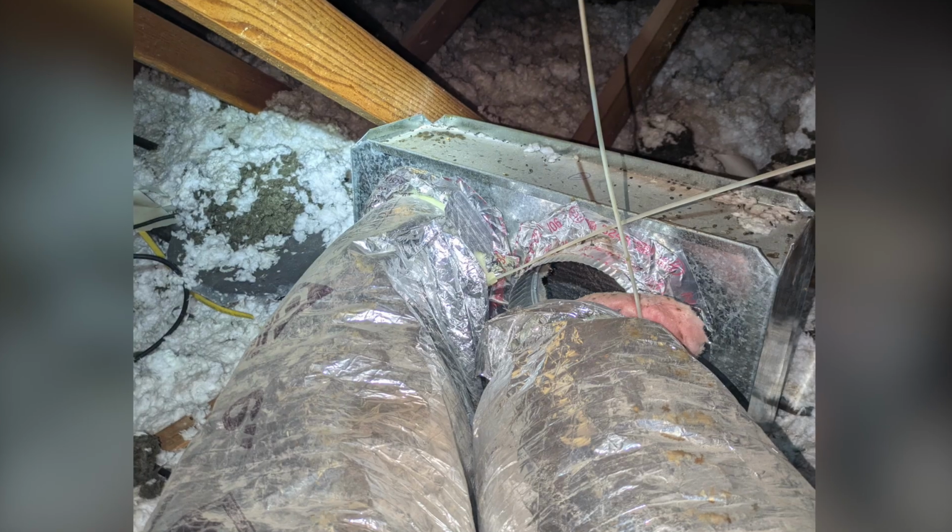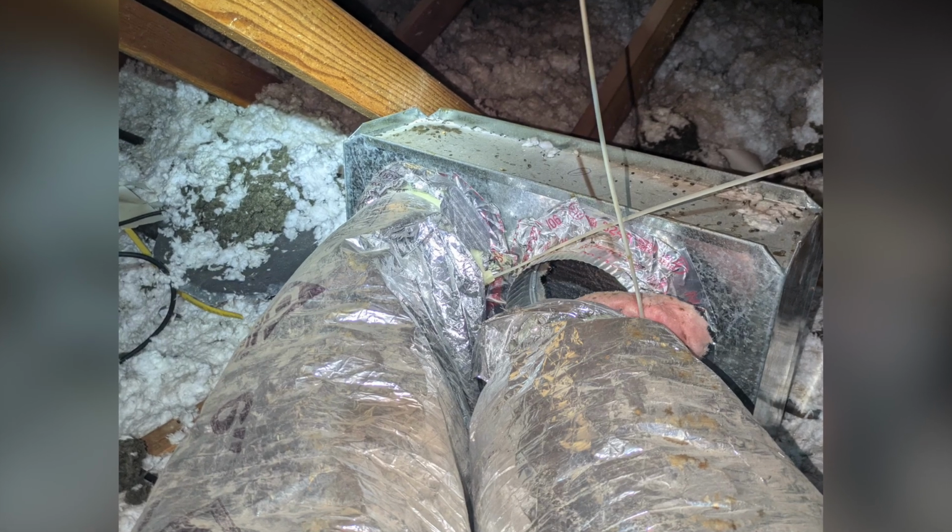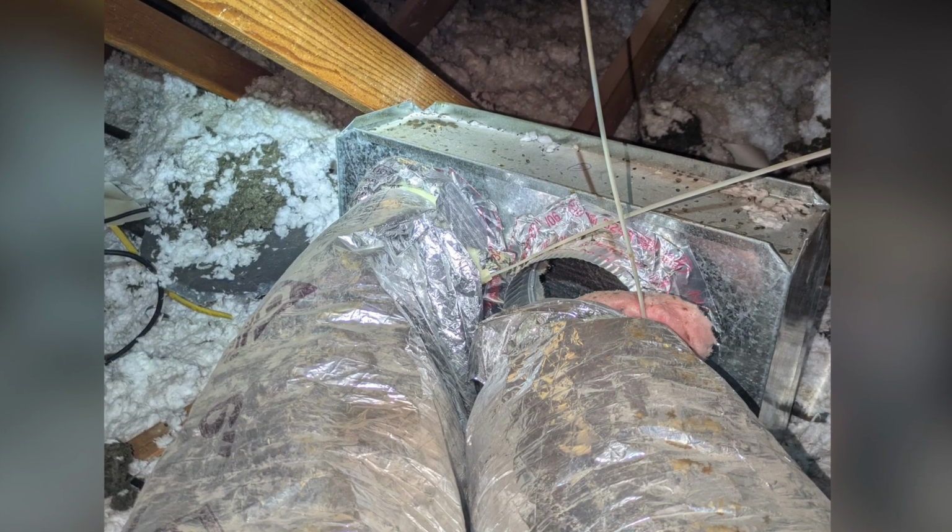When Matt Callender from Advantage Home Performance showed up, he actually asked if he could go up into the attic and look around. At least 9 out of 10 houses we go in have some sort of problem with the ductwork, whether it's undersized returns or ductwork that didn't get sealed properly during installation. We found a lot of the typical duct leakage you'd find around the beginning of ducts, and we also found what we would call a catastrophic duct leak, which was one of the larger ducts completely disconnected. The disconnected duct in Julia's attic led to a lot of her comfort issues and higher utility bills.